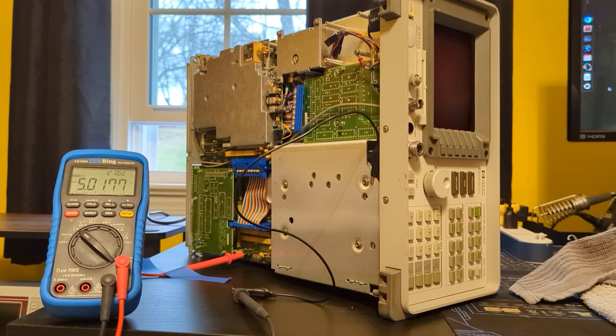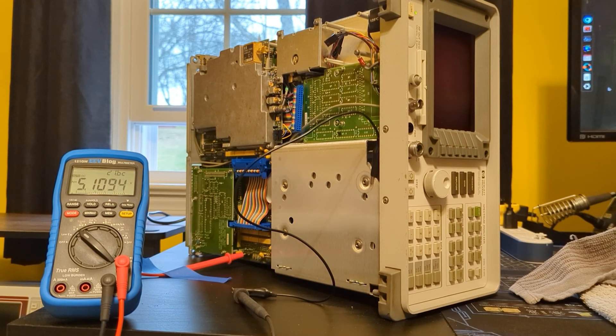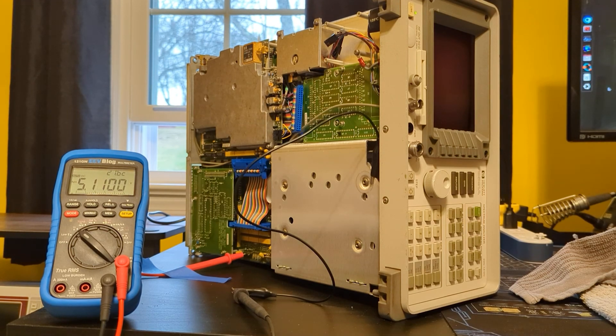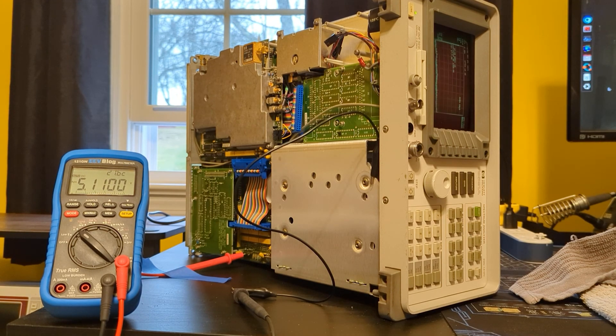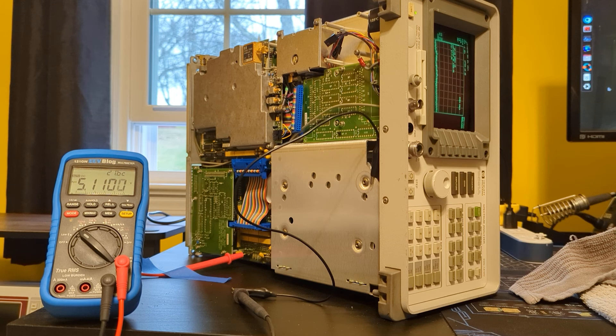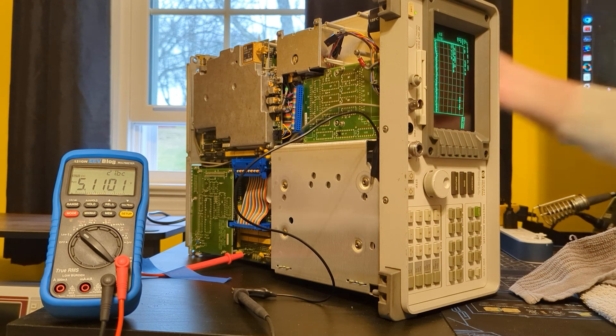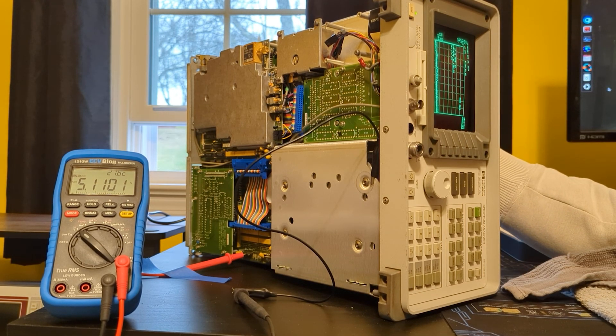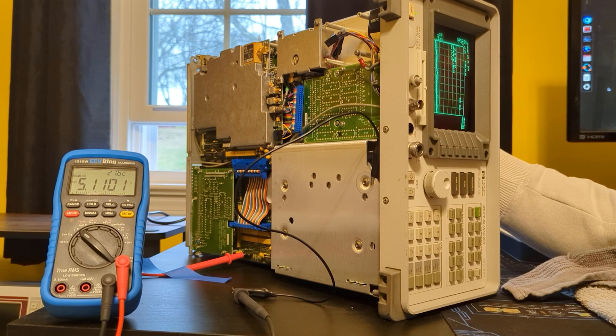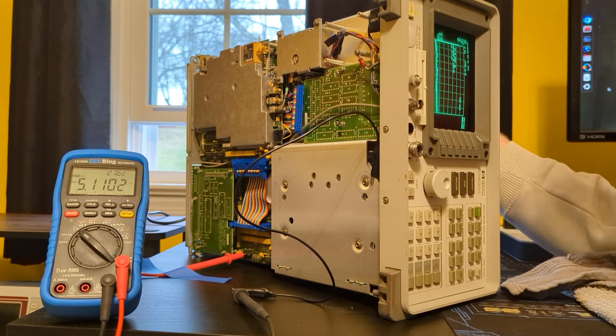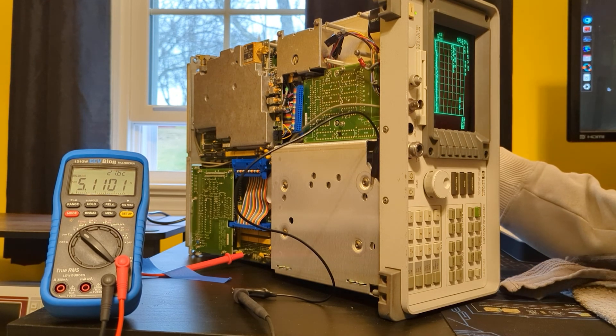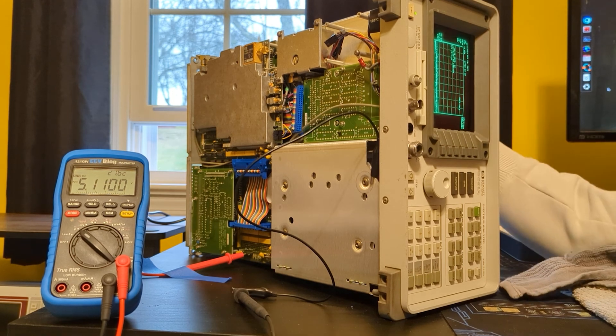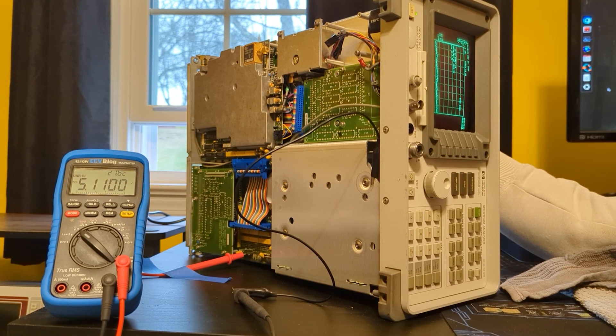This shows I'm turning on the unit and doing a final check. The key voltage with this thing is you want 5.1 volts on the power supply when it's running. You can see I'm adjusting this. It wants this to be very precise before I run the calibration, so you can see I'm adjusting to get it really right on.